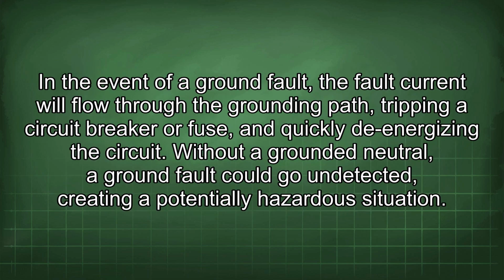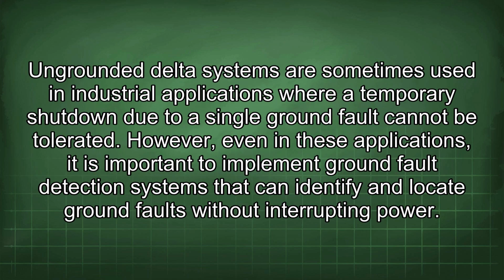In the event of a ground fault, the fault current will flow through the grounding path, tripping a circuit breaker or fuse, and quickly de-energizing the circuit. Without a grounded neutral, a ground fault could go undetected, creating a potentially hazardous situation. Ungrounded delta systems are sometimes used in industrial applications where a temporary shutdown due to a single ground fault cannot be tolerated. However, even in these applications, it is important to implement ground fault detection systems that can identify and locate ground faults without interrupting power.